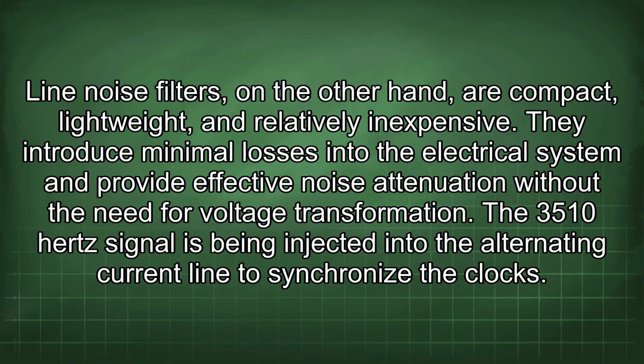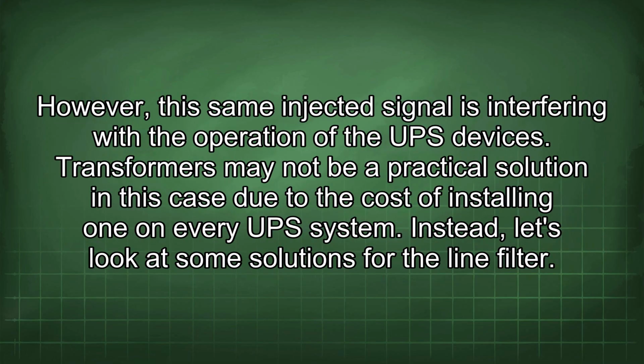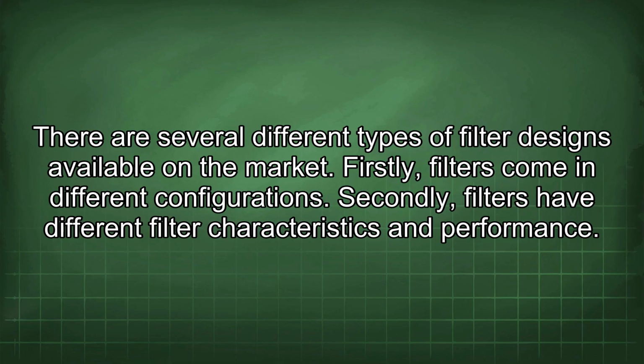The 3510 Hz signal is being injected into the alternating current line to synchronize the clocks. However, this same injected signal is interfering with the operation of the UPS devices. Transformers may not be a practical solution in this case due to the cost of installing one on every UPS system. Instead, let's look at some solutions for the line filter. There are several different types of filter designs available on the market.